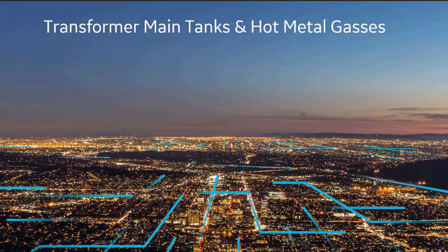The point of having—for example, if you look at some of the studies that have been done, like out of CIGRE, and you look at the percentage of transformers that actually had issues, either from a failure standpoint or a repair standpoint—you still go back to the point that you had a large portion that might have been winding. Well, what's in windings that really causes things like that? Or ultimately, you end up failing the winding, and a good bit of the time it's the paper, right?